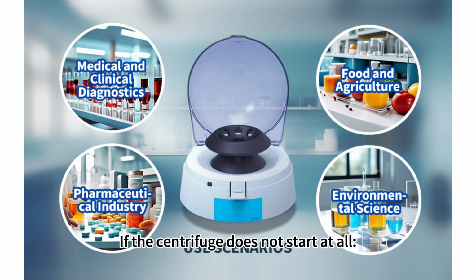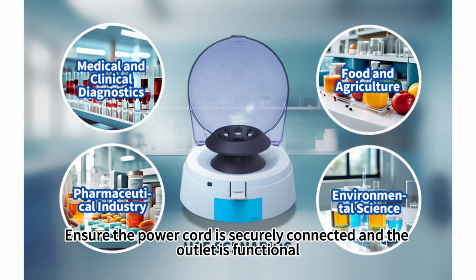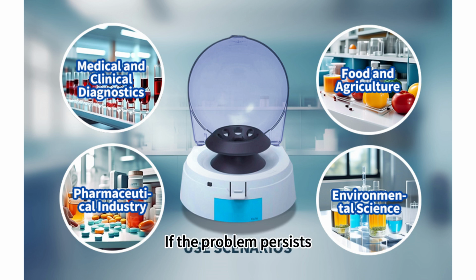Power failure. If the centrifuge does not start at all, solution: ensure the power cord is securely connected and the outlet is functional. If the problem persists, check the fuse or circuit breaker.